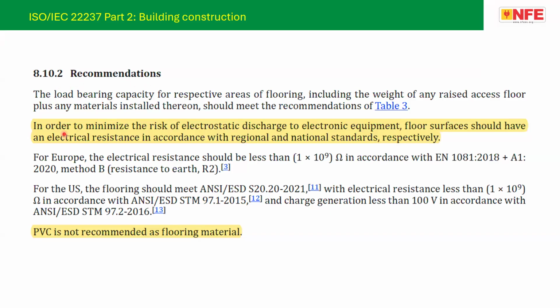You can see here. In order to minimize the risk of electrostatic discharge to electronic equipment, floor surface should have an electrical resistance in accordance with regional and national standards. Unfortunately, the national standard in India is a little bit old, but there is an IEC standard which is already in discussion in India, which gives you very clear idea how to protect electronics from electrostatic charges. Then the PVC is not recommended as a flooring material. I'm just showing you some of the examples.